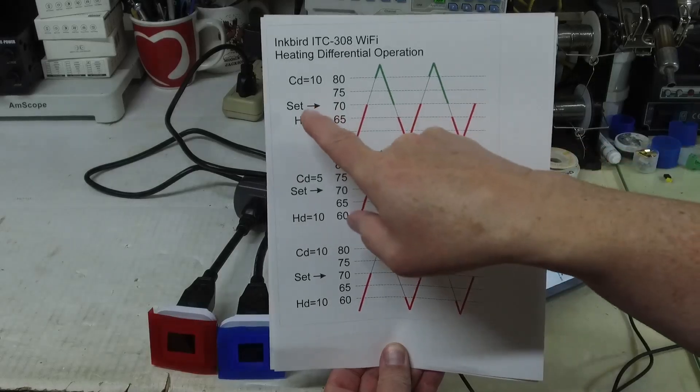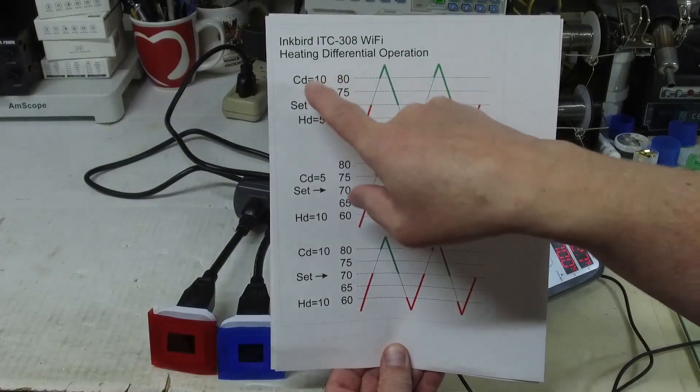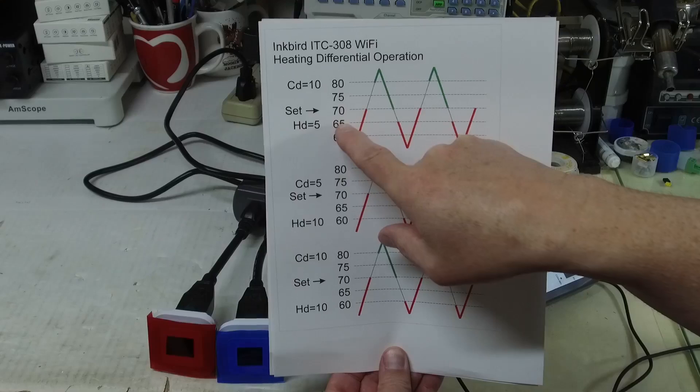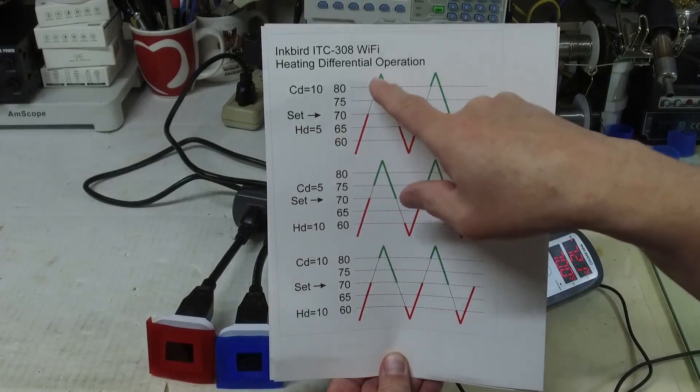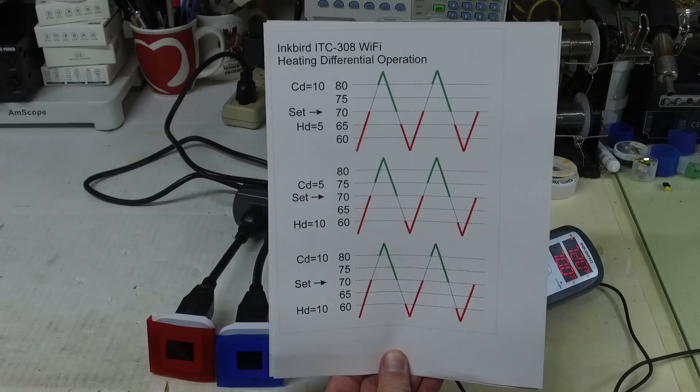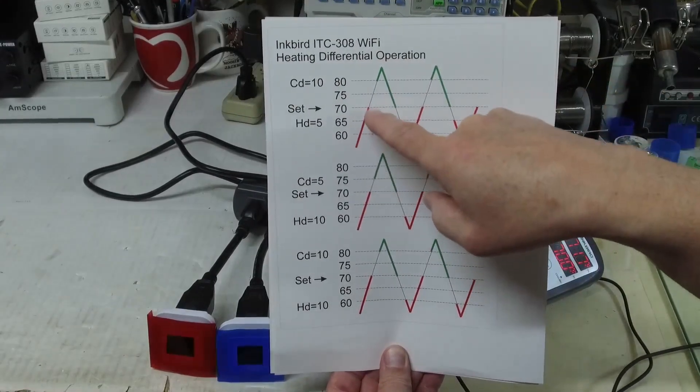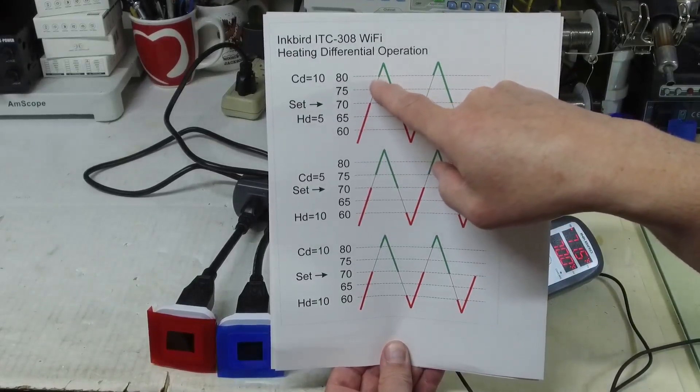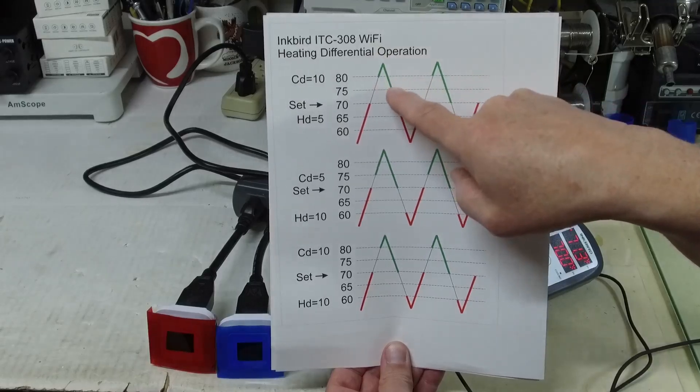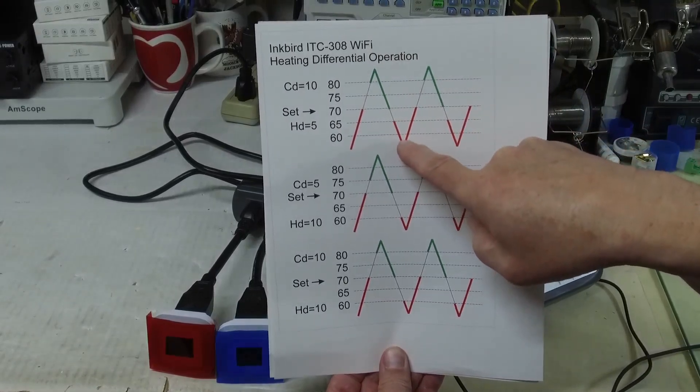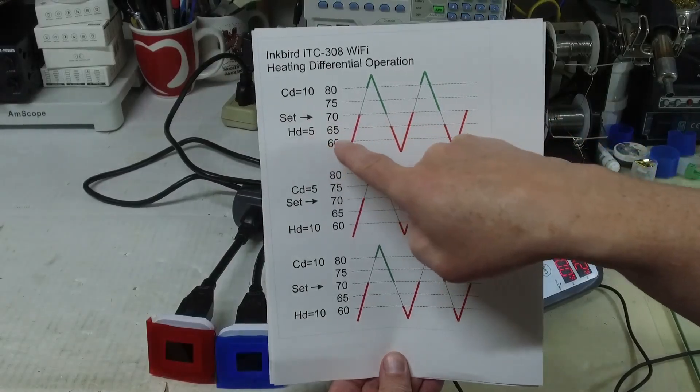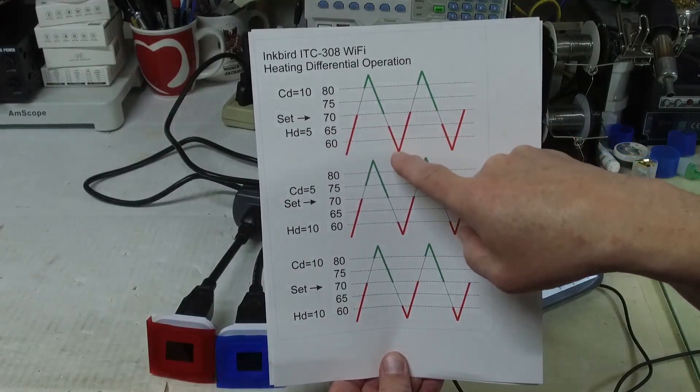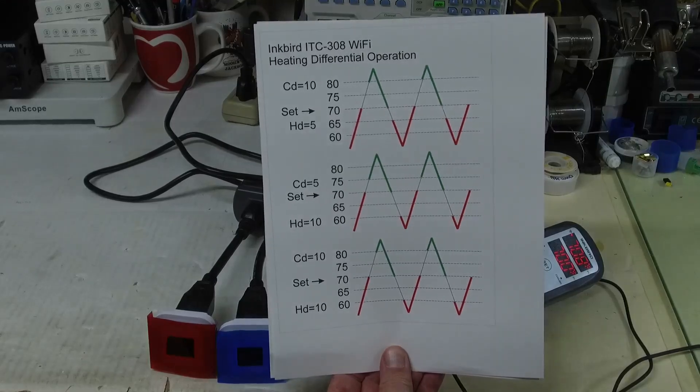So in this scenario I have the set point at 70 degrees and I have the cooling differential at 10 and the heating differential set at 5. The red is showing where the heater will turn on and green is where the cooling will turn on, and this is a representation of the temperature swings. When this temperature hits 80 degrees the cooling turns on and it will keep the cooling on until it hits the set point. When we are cooling down even further, we can see that the differential here is 5 degrees, and so the heater turns on at 65 but will not turn off until it hits 70.